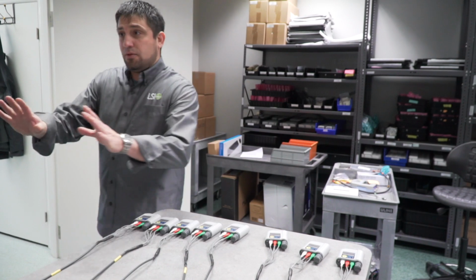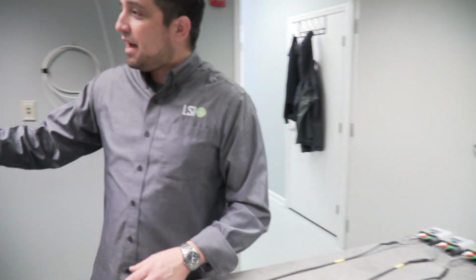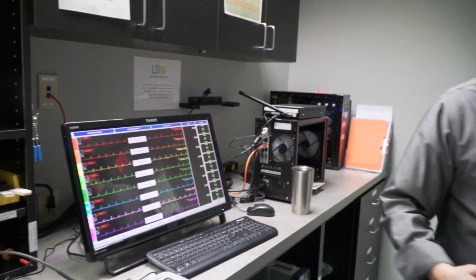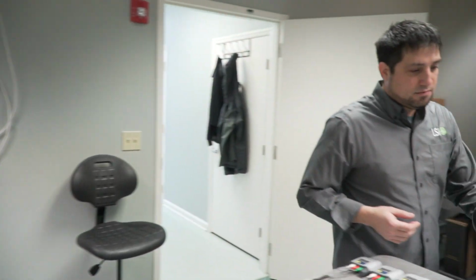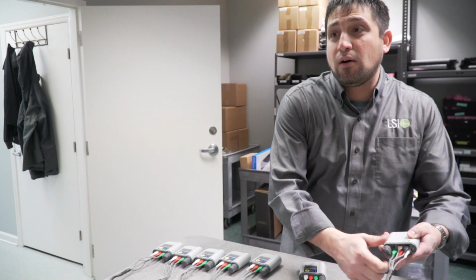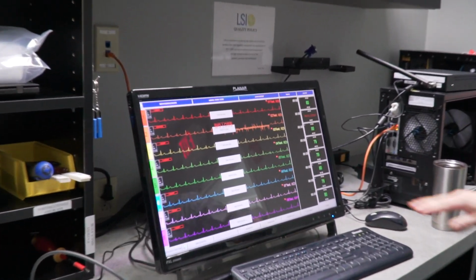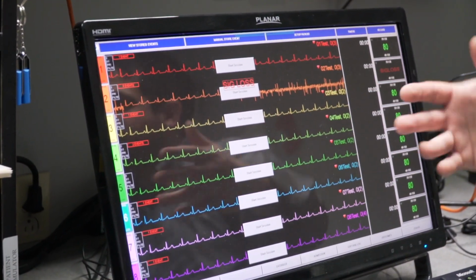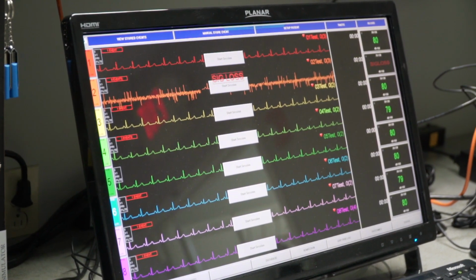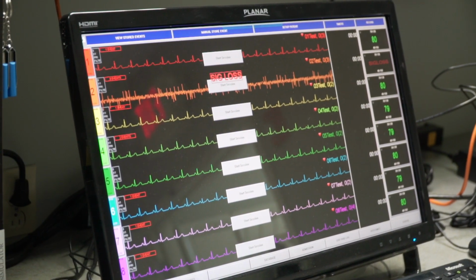And so we send all those out back onto this screen, and we have 8 results. So if I were to remove power from one of these transmitters, we would notice that we have sig loss. So it's basically saying we've lost transmission. So we're able to verify that individual channels are down.